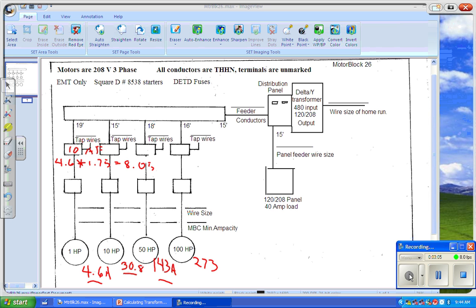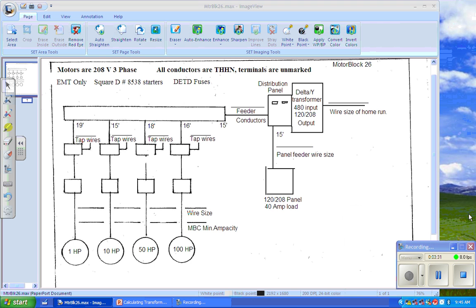Okay. And C, control circuit transformer, our favorite, where a motor control circuit transformer is provided. The transformer shall be protected in accordance with 430.72 C1, C2, C3, C4, or C5. And so that's our column C. And so our separate control, we can have different size wires.